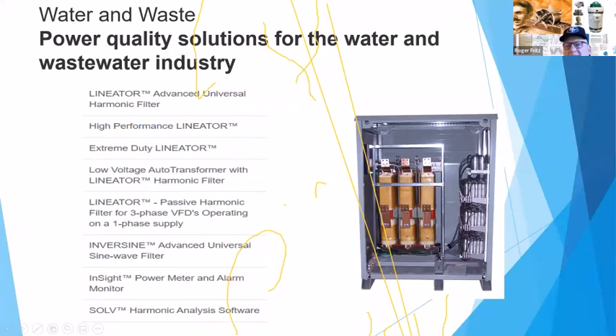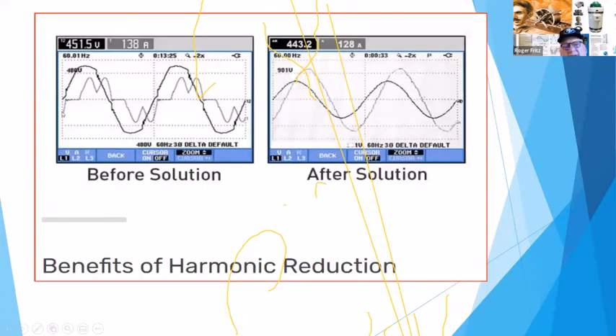And those coils resist change in power. So as you put power to them, an inductor doesn't want to immediately take it. It has a delay. Well, then they also put capacitors on here that are tuned in microfarad size, that are connected in parallel across the circuits. And what that does is it actually absorbs some of those higher frequency information, and those have to be more what they call a tuned filter. The resultant is that it actually cleans it up.